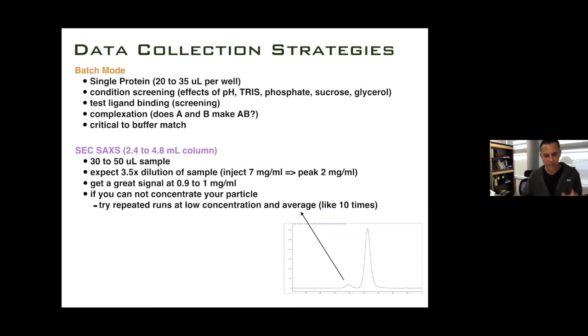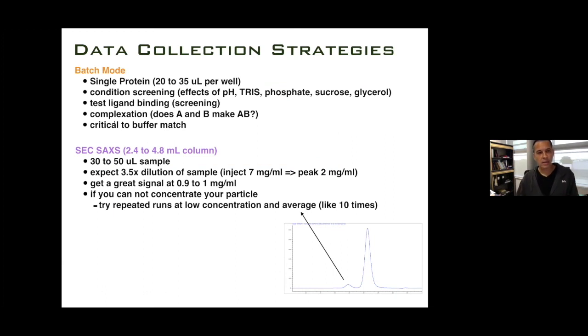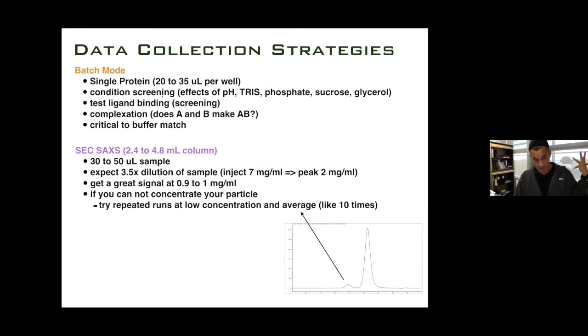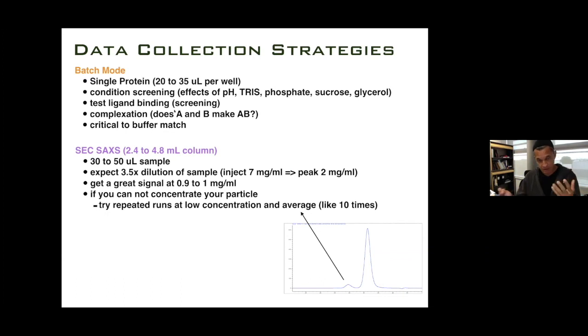The two kinds of data collection we process with Scatter are batch mode experiments, where you prepare samples in a plate and manually load them into a cuvette with typical sample volumes of 20 to 35 microliters per well. This is good for condition screening — looking at a variety of different pHs, different buffers, additives like sucrose and glycerol, ligand screening, or asking whether protein A mixed with protein B forms a complex.